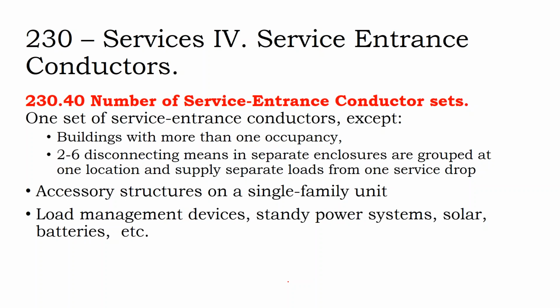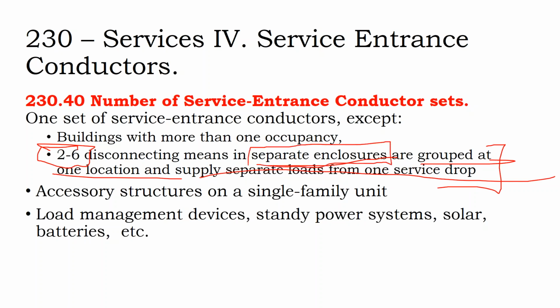You're supposed to have one set of service conductors unless you are not using one main disconnect and you have up to 6 disconnects in separate enclosures that are grouped at the same location. So if you're just doing a main lug only panel, the disconnecting means might not be in a separate enclosure, but this might be if you have a service and it's running out to 6 separate fused disconnect switches. You have one set of service, you could have 6 sets coming off of that transformer if you wanted to. Or buildings with more than one occupancy. I mean, it's pretty lenient.